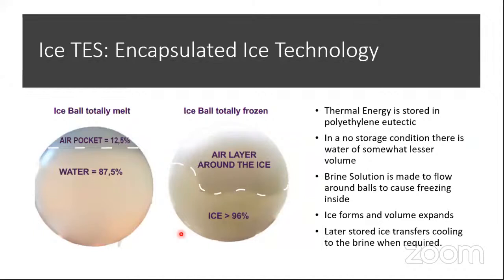And then there's another category in ice thermal storage, encapsulated ice technology, where chilled water is encapsulated inside capsules. Although there are different models available out there, more or less it's like this. The water filled inside is generally 85, 87%, something like that, and there are air pockets as well. So when the ice is made, there happens some expansion in the volume. So the entire capsule is occupied by nearly 96% of the ice, and the remaining is air. So that is encapsulated ice technology.